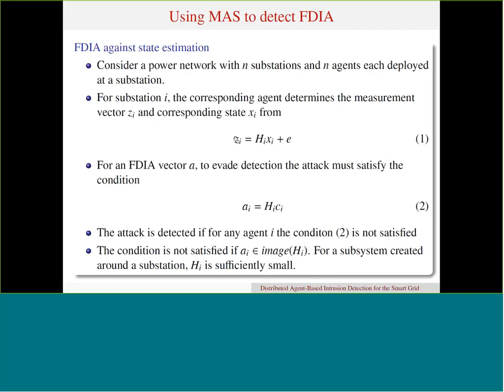The power grid generally has defenses against false data injection attacks. There are two things: chi-squares, and running the L2 norm to determine if there's data that falls outside a certain bound, and that's how the power grid normally detects attacks. But there's a class of false data injection attacks that evade detection if it's done in that fashion. So we're saying if we do distributed state estimation, false data injection attacks against measurement data will not pass this bad data detection. As a result, we would greatly reduce the success rate for false data injection attacks when we do state estimation at the agent level for just a small section of the power grid.